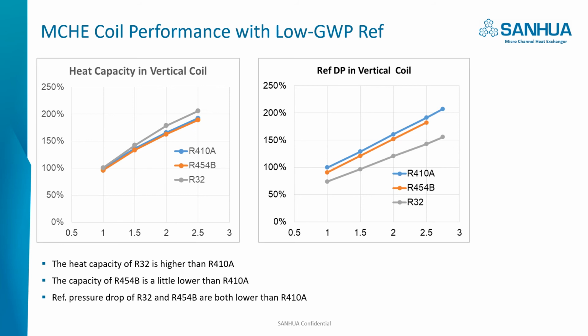This slide shows the microchannel performance with low GWP using the vertical coil. The left chart shows the heat capacity, and the right chart shows the refrigerant pressure drop. For this vertical coil, we tested R410A, R454B, and R32. The result shows the heat capacity of R32 is higher than R410A, and the R454B capacity is a little lower than the R410A. Looking at the refrigerant pressure drop, the R32 and the R454B are both lower than the R410A because of the mass flow. Both are lower.